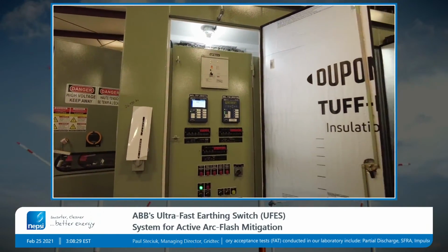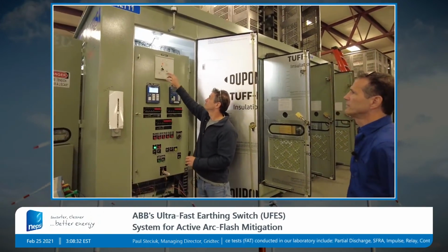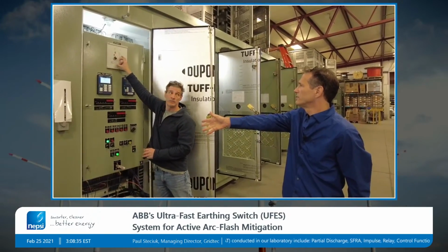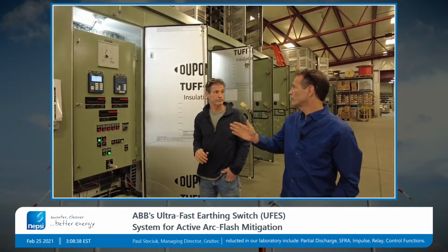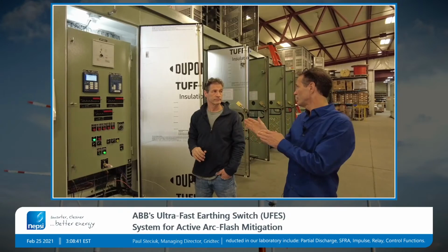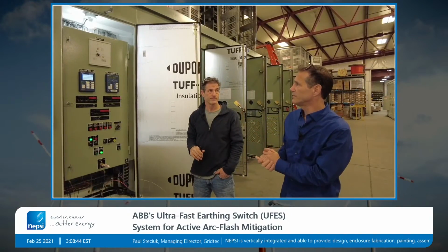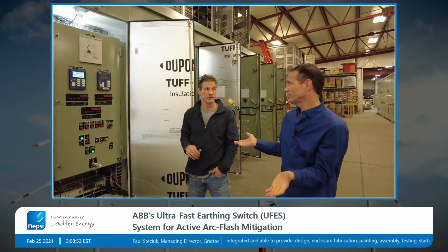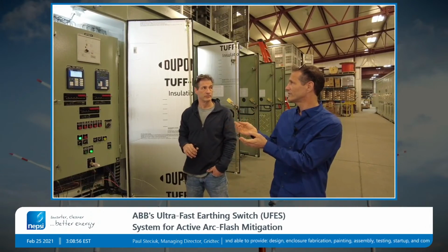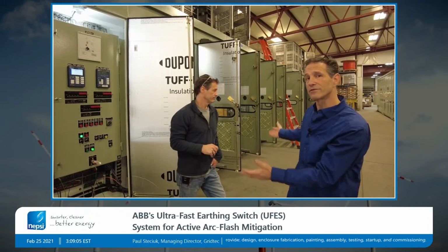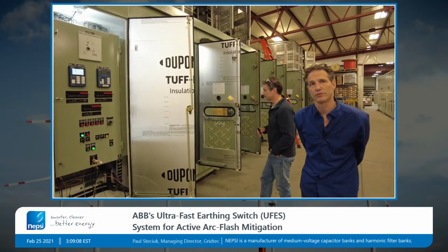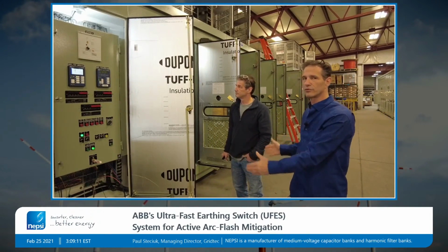So in the end, if this was a real short circuit condition, the power switching elements would have brought the bus bars to ground. It would have resulted in a transfer trip to the upstream breaker, as well as this breaker here. Yes. And to put the system back in operation, you'd have to purchase 3 more switching elements, Yes. install those, Yes. and you'd be good to go. But the assumption here is that the fault current is significantly reduced, the time duration is significantly reduced, and therefore the damage is significantly reduced. Incidentally, this is an important piece of equipment. It's expensive. So the purpose is to reduce damage and also improve the safety for workers that work around the equipment.